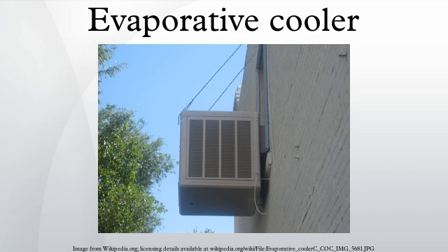Typical installations. Typically, residential and industrial evaporative coolers use direct evaporation, and can be described as an enclosed metal or plastic box with vented sides. Air is moved by a centrifugal fan or blower and a water pump is used to wet the evaporative cooling pads. The cooling units can be mounted on the roof, or exterior walls or windows of buildings.